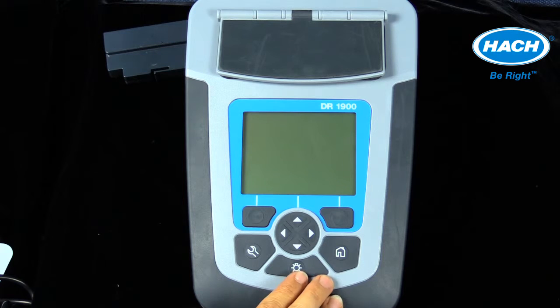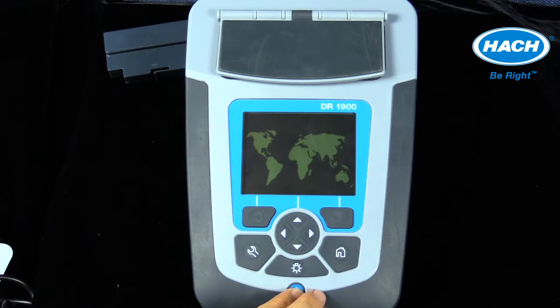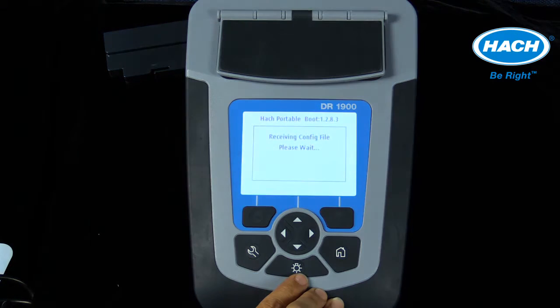Power on the DR1900. The meter will display the Hach portable version at the top and the words "receiving configuration file. Please wait," with a spinning flask. After a minute, the display will change to "updating configure files" to config_.pzip with a spinning flask. Then the meter will beep and the display will change to "receiving firmware file. Please wait."